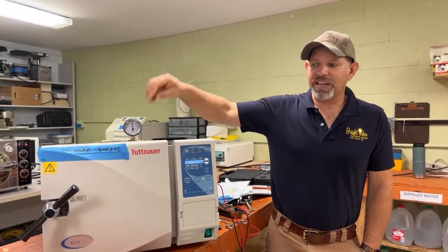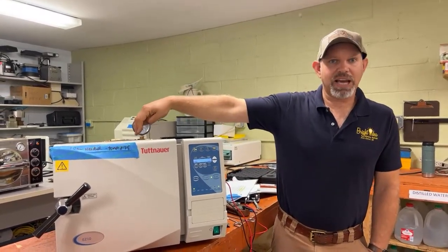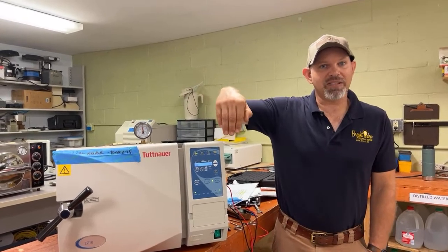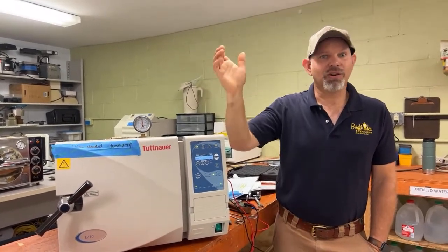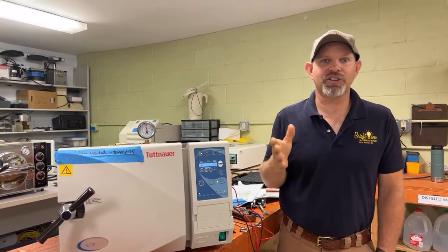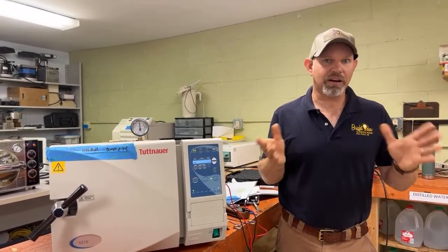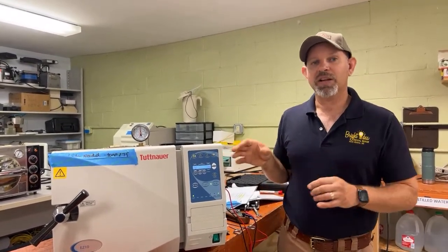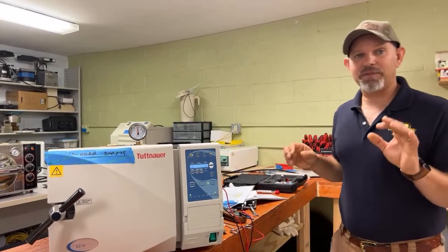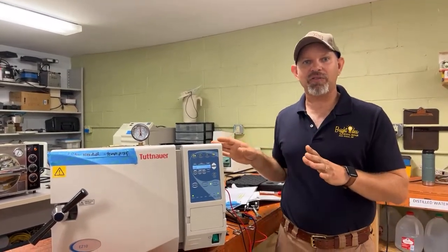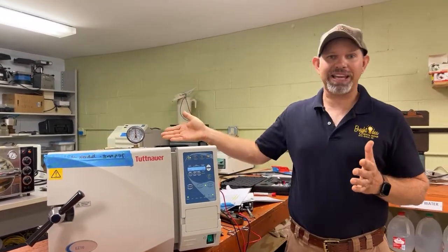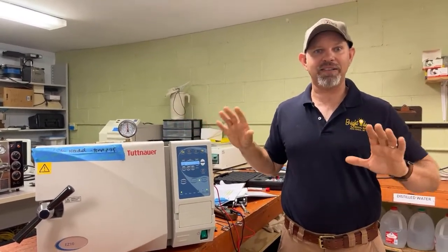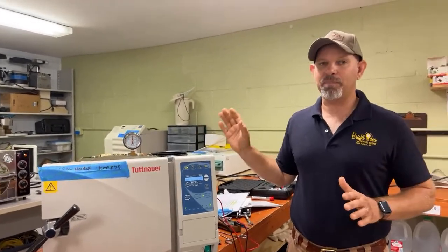If your standard, your thermometer, matches what the display is, I would go ahead and sign your paper off and you're good to go. It's when there's a deviation or an error or something that's going on that's amiss that I would run this. Now, if you're doing any of these sorts of repairs, the RPI kit is indispensable, because just being able to throw a gauge on and see where you're at is really important.